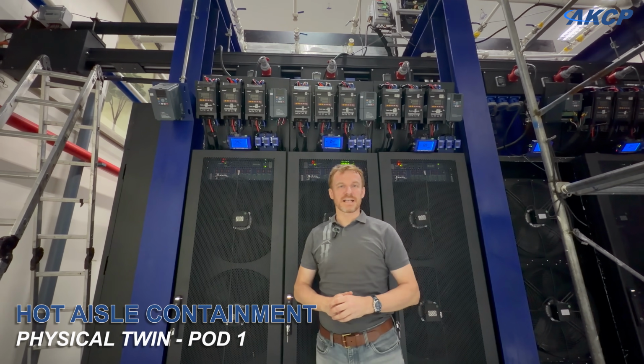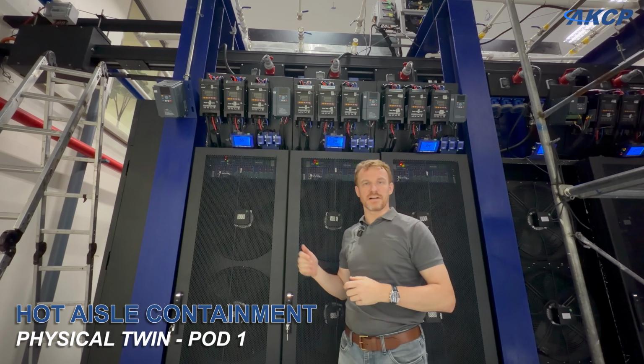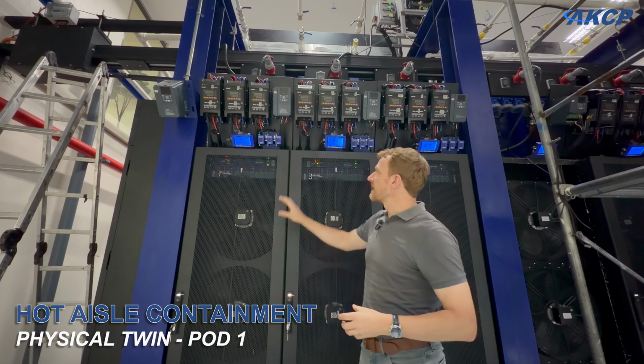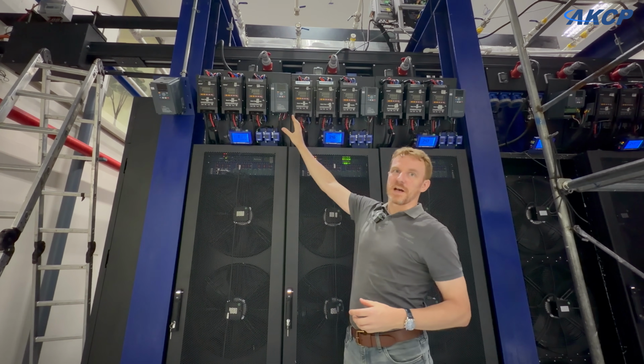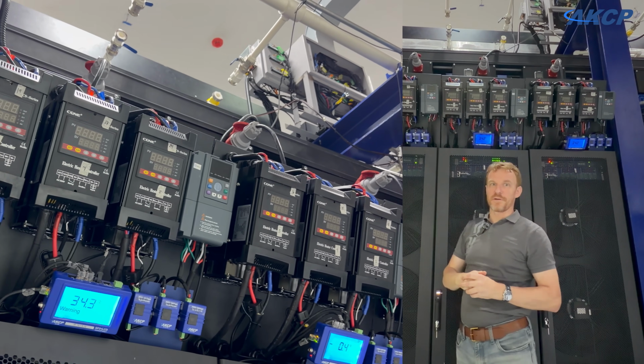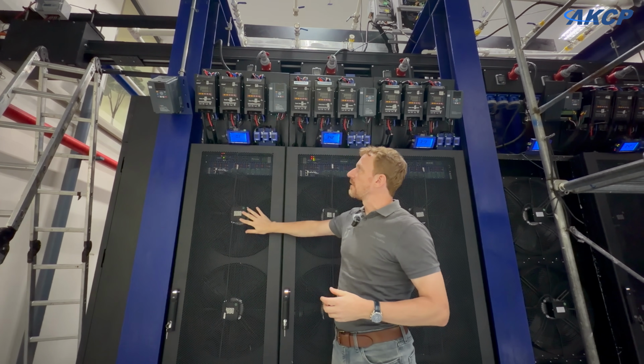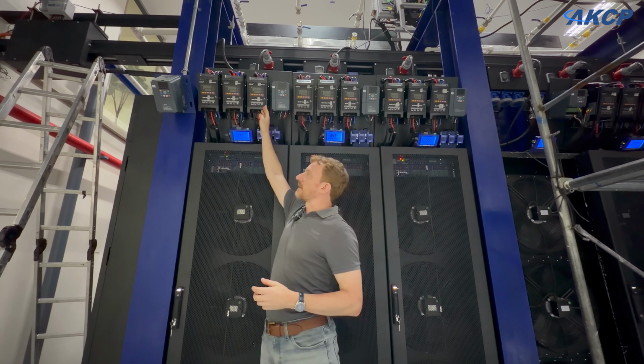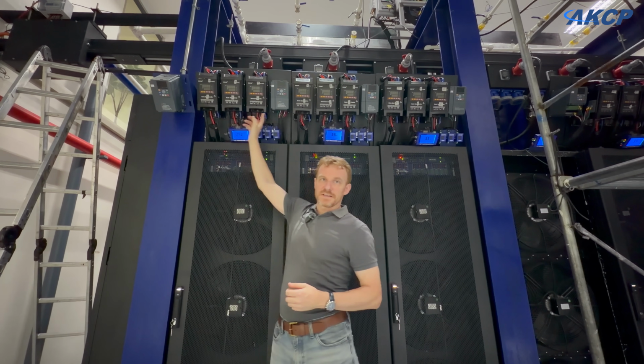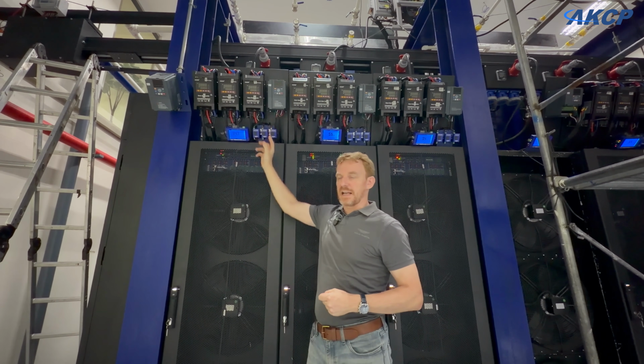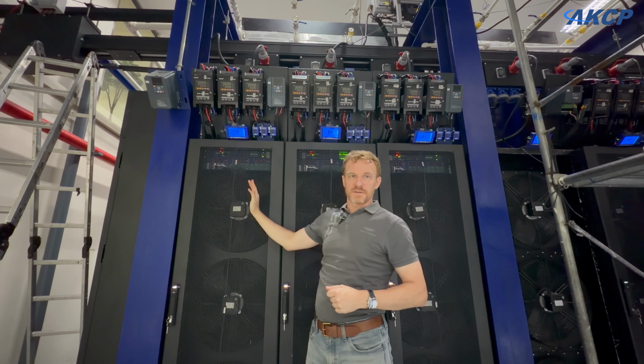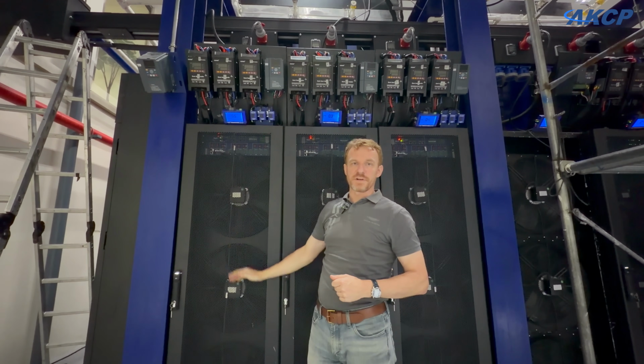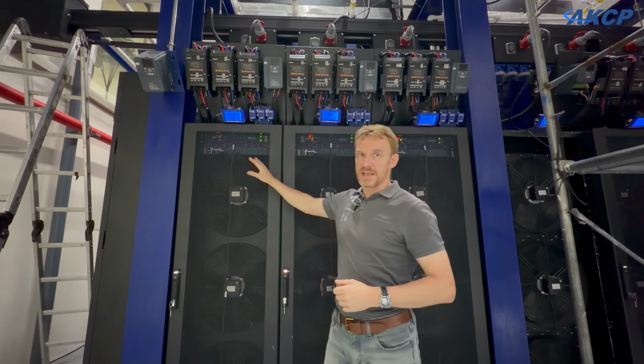So here we are in our test data center with our hot aisle containment pod. You can see now we've added a lot of equipment up here that wasn't in our previous video. What we've got now on each rack, we've got 3 PWMs. This is a pulse width modulator that allows us to control the amount of kilowatts of heat going to each one of the fans, so each one of the heaters.